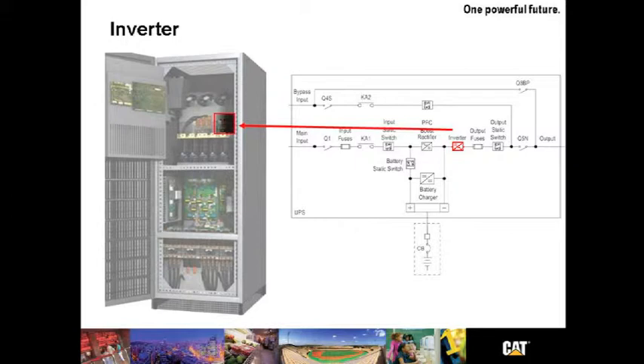The inverter operates at a variable chopping frequency of approximately five kilohertz. During steady state, the output voltage will be held within one percent of the RMS values of the phase-to-phase voltage. During an overload situation, the load is immediately transferred to bypass. During a transient event from the load, the UPS will handle a hundred percent load step with no more than two percent voltage change in RMS values phase-to-phase. The transient response to within plus or minus one percent range of RMS value is less than a hundred milliseconds.